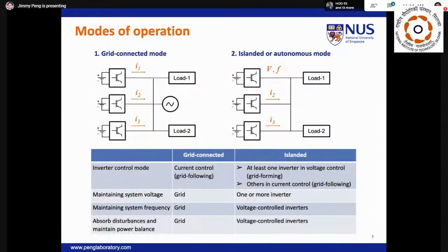So a microgrid can operate under two different modes, that is, grid-connected mode and islanded mode. Under grid-connected mode, the frequency and voltage regulations are managed by the utility grid. In other words, all inverters within the microgrid are simply following the main grid.